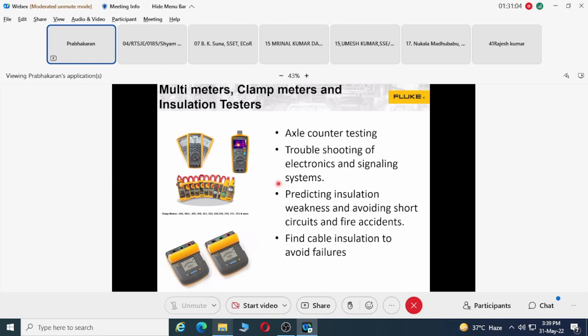From my own interactions with your colleagues or Indian Railway officials, I understand that the cabling and installation of communication or signaling cables need to be tested on a periodic basis, maybe every 6 months, 1 year, or 3 years, to ensure everything is working, because insulation of any material can change due to various conditions like over temperature, over voltage, vibration, dust, or humidity.